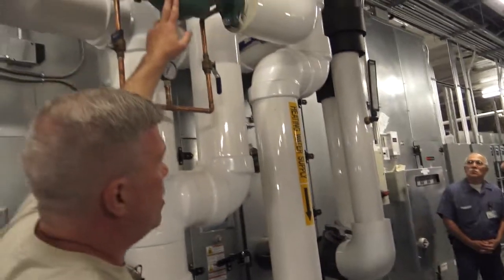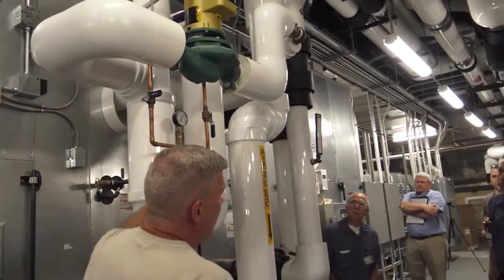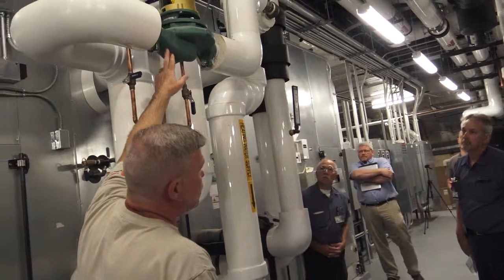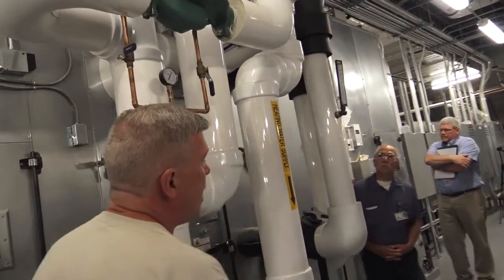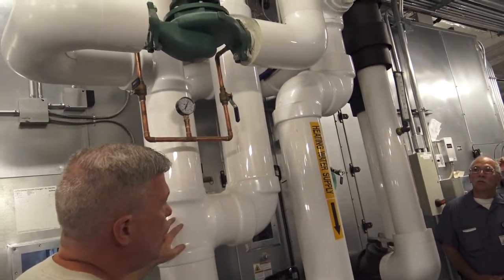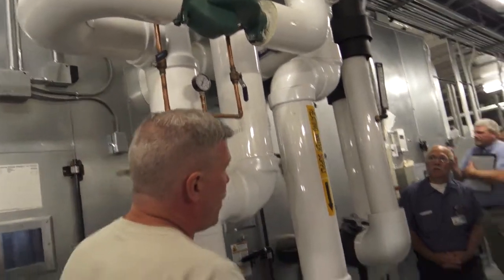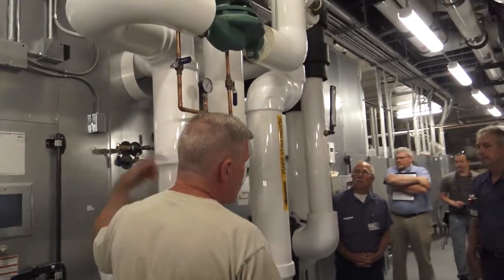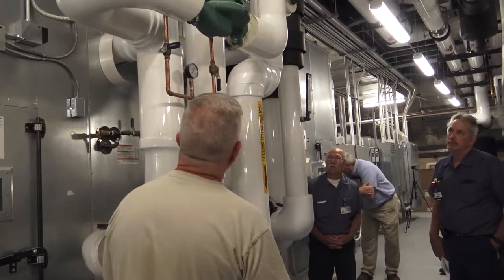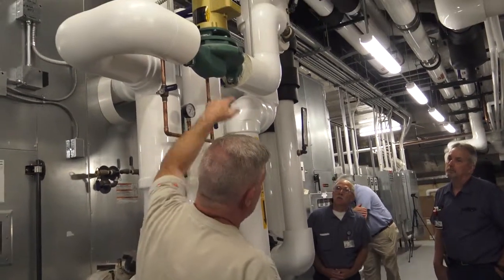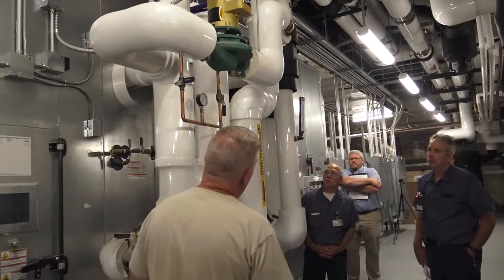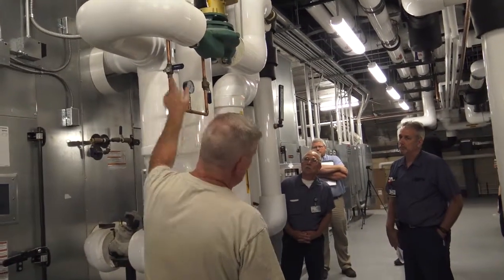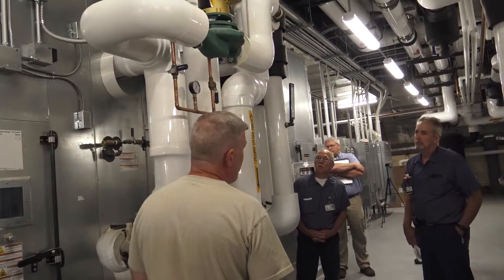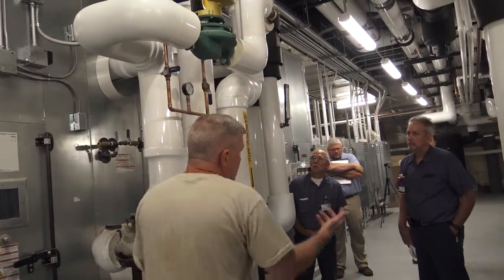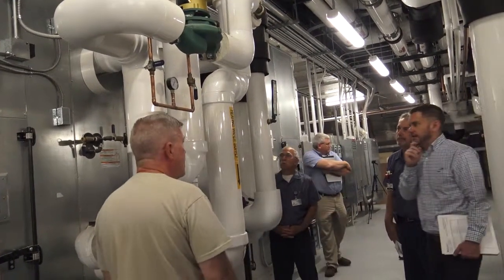And then the hot water coil section does have a little coil pump that'll run anytime it's below 40 degrees out. This pump will just circulate water through the coil at all times. Also, when the air handler is shut off and it's below 40, the valve will stay wide open, circulating hot water through it all the time. So this is just freeze protection again. If this fails and you bring in any cold air, it'll just keep water circulating, trying to keep the coil from freezing.